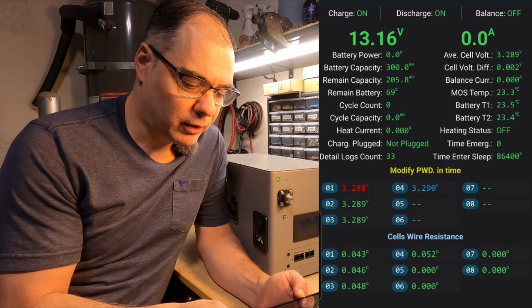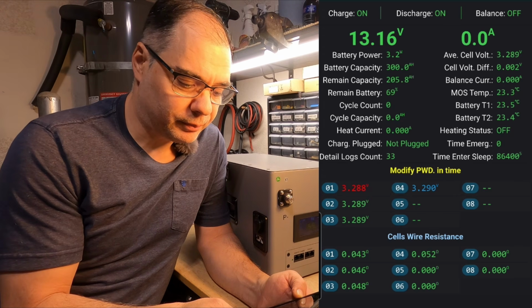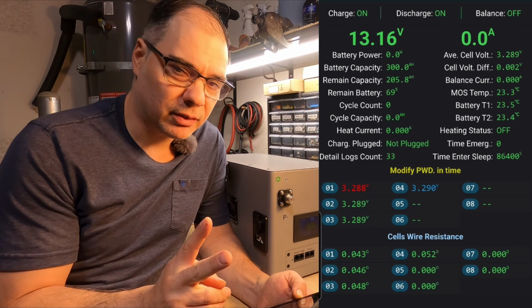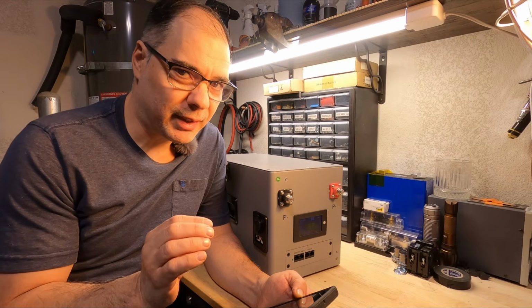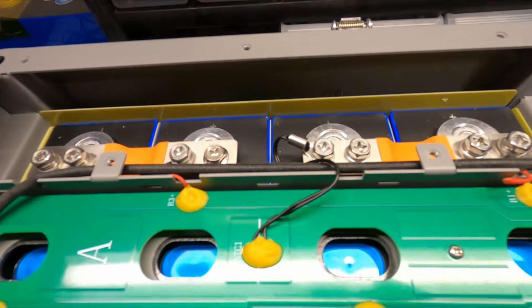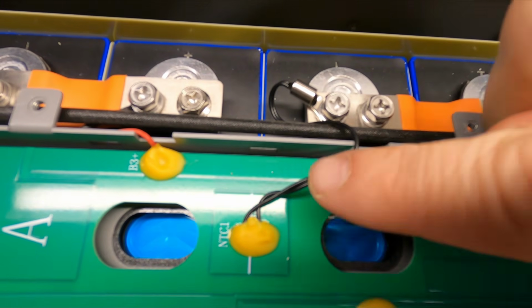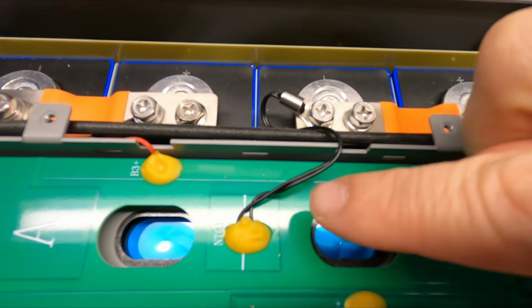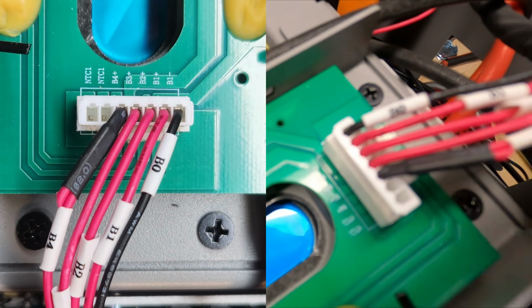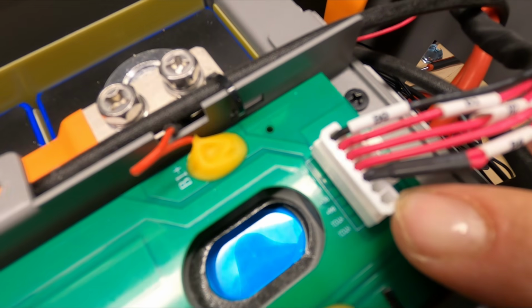We have all 4 cells registered. Battery T1 and T2. So there's only 2 temp sensors. So we're going to have to investigate whether the one on the PCB is actually being used or not. You can see right here on the PCB rail, the temp sensor is labeled NTC1. If you come over here to the pinout on the connector, you can see NTC1 is empty, not connected. So apparently the temp sensor on the PCB rail does absolutely nothing. Perhaps they should change it to NC1, not connected one. Or maybe NTC1 means not connected one.